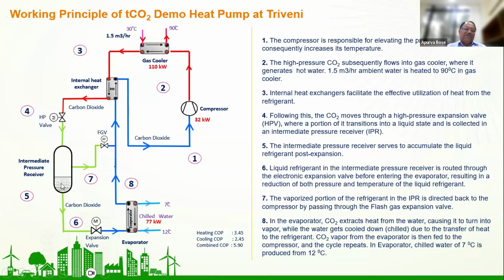When we talk about the liquid CO2, it comes out and passes through an expansion valve. Here both the pressure and the temperature come down, and the temperature is normally around 3 to 4 degrees Celsius. So the water which we get, let's say from a chiller or from anywhere else, at 12 degrees Celsius, it gives back at 7 degrees Celsius. And the CO2 again goes back from here to the compressor. So this is how it works.